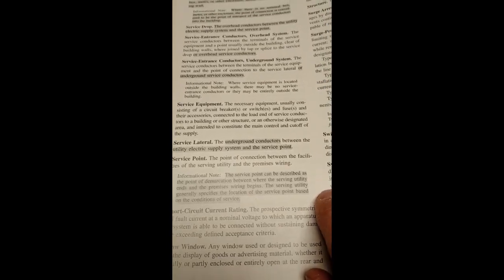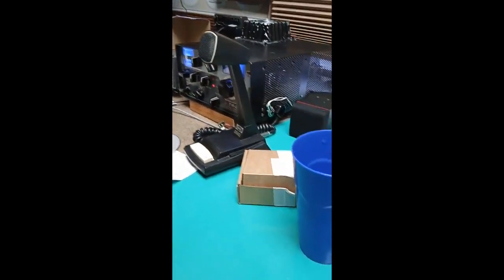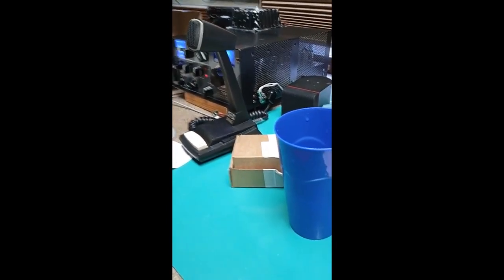The necessary equipment usually consisting of a circuit breaker or switches and fuses, a fuse breaker or switching box, and their accessories connected to the load end of a service conductors to a building or other structure or an otherwise designated area and intended to constitute the main control and cutoff of the supply. Service equipment is not a load device, which is a radio transceiver. Therefore, it is absolutely, in every case, wrong to ground that. And again, it is 2 violations of 250.24(A)(5), and there it is.